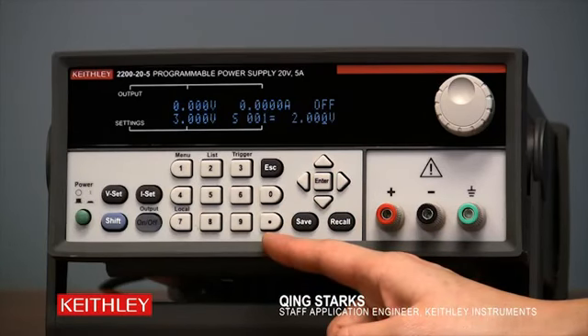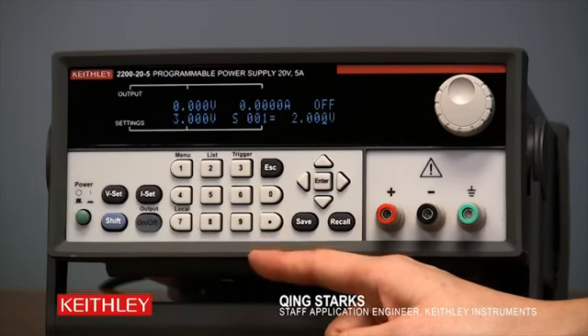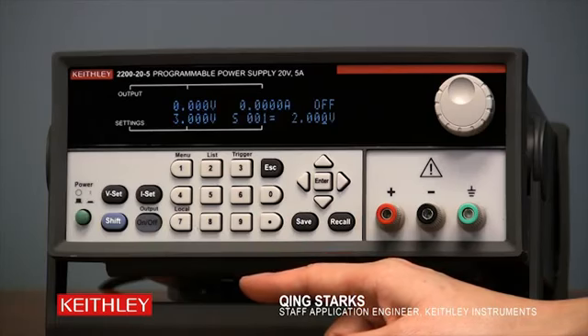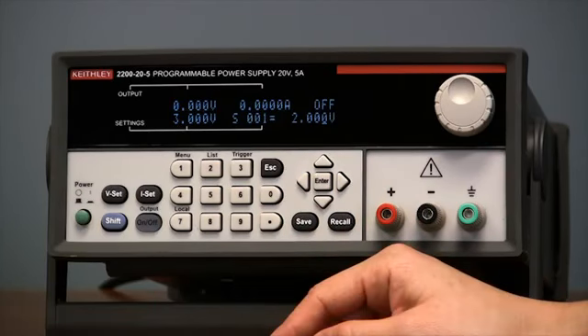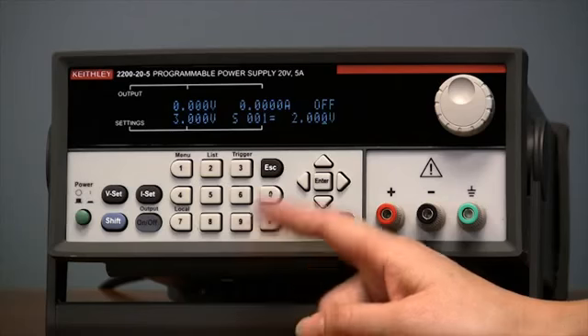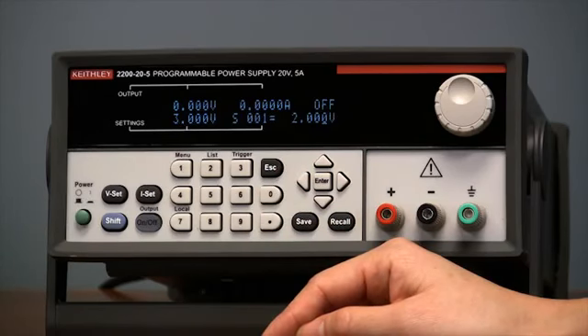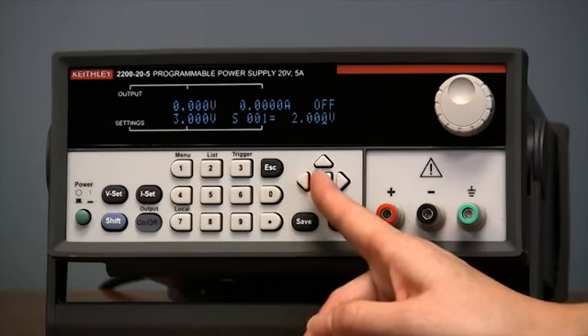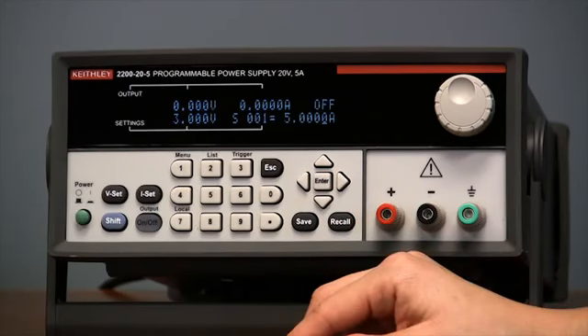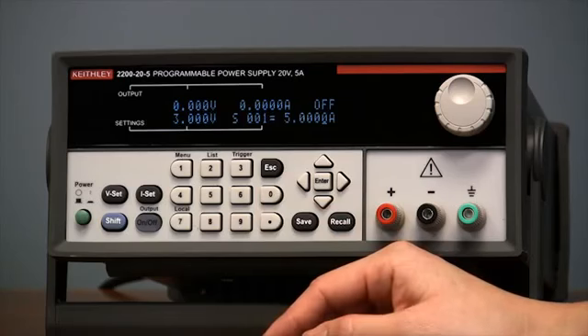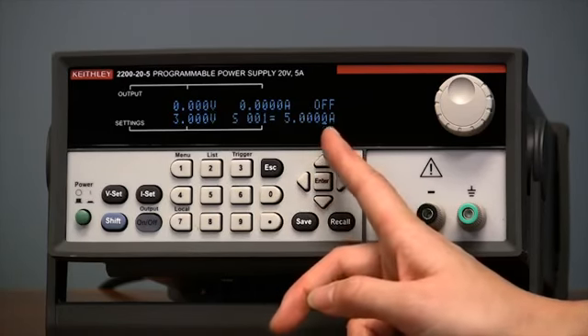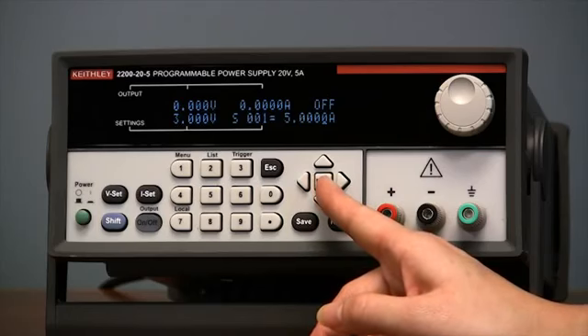Now we're going to configure each individual step in the list. The display is now showing S001, which means step 1, and the first number is the voltage setting. It is currently at 2 volt, and we're happy with that. We'll just press Enter. The next step is entering the current limit for this particular step. It is currently at 5 amps, and we'll just press Enter.